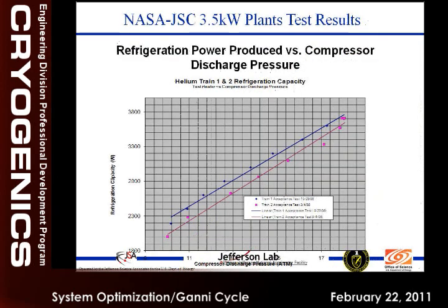And then they used to tell us, we are designing these plants, and once we know one plant, that's what we need. They have 3.5 kilowatt plants. This is where I was telling you, all plants don't have the same tolerances when you build. So the optimums are not the same. Although they are both mass-produced plants, the compressors, turbines and heat exchangers have different tolerances when put together, so one has a different optimization than the other. By allowing it to float and relax, it seeks its own optimum.